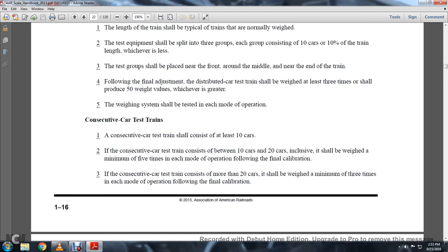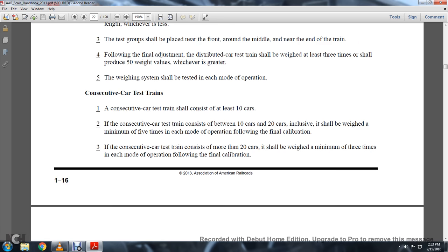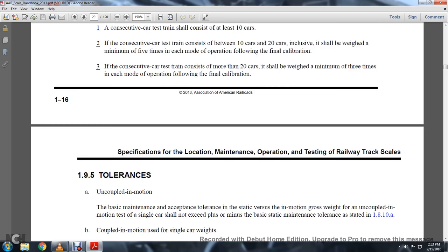The consecutive car testing train consists of at least 10 cars. A consecutive car testing train consisting of 10 to 20 cars, inclusively, shall be weighed a minimum of five times each mode of operation following the final calibration. If the consecutive car train consists of more than 20 cars, it shall be weighed a minimum of three times in each mode of operation following the final calibration.